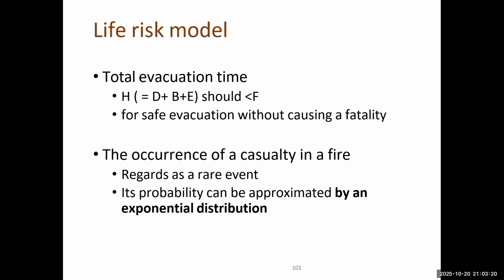So this brings us to the core concept of the total evacuation time. For a safe outcome, the entire process must be completed before the environment becomes very dangerous. This is summed up by a critical inequality. The total evacuation time, H, is equal to D plus B plus E, and must be less than the tenability time F. If the condition is met, the occupant reaches safety in time, and if not, they are exposed to untenable conditions.